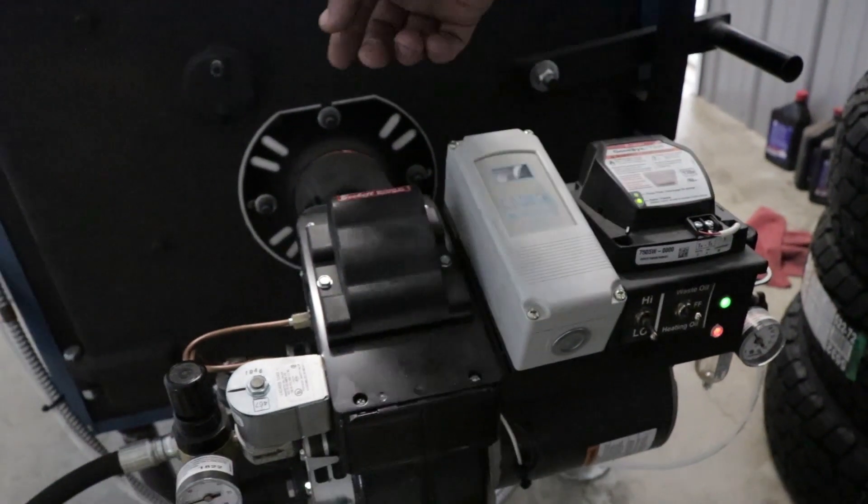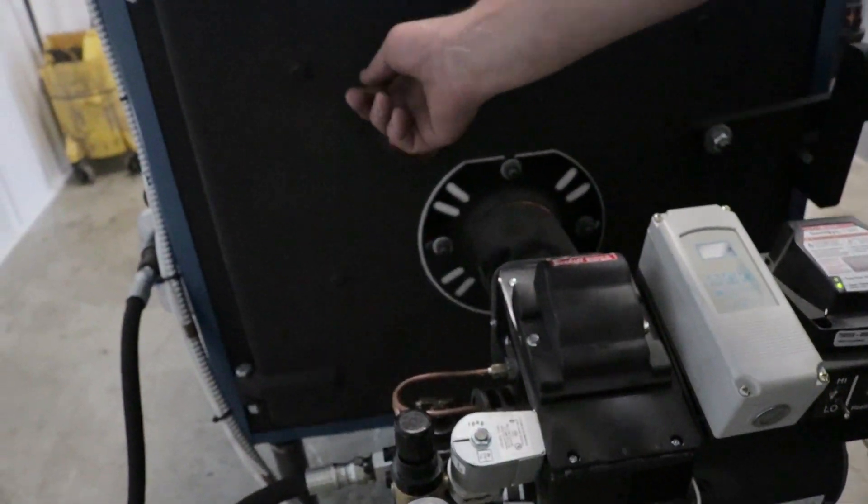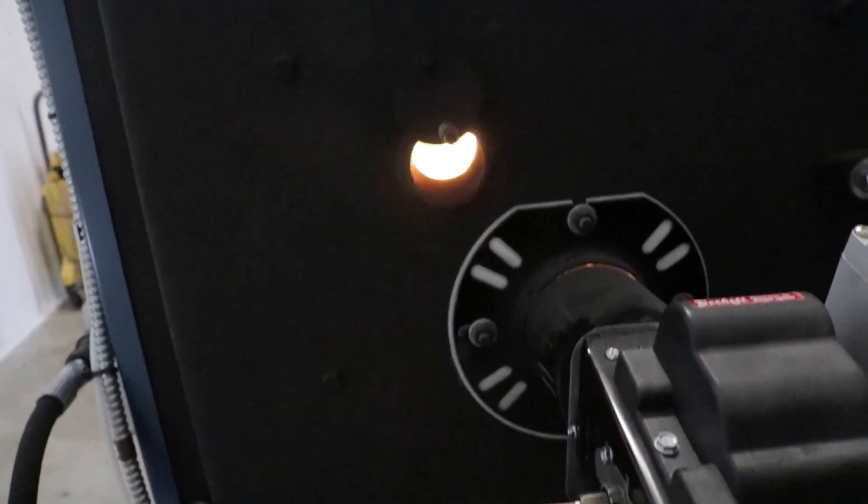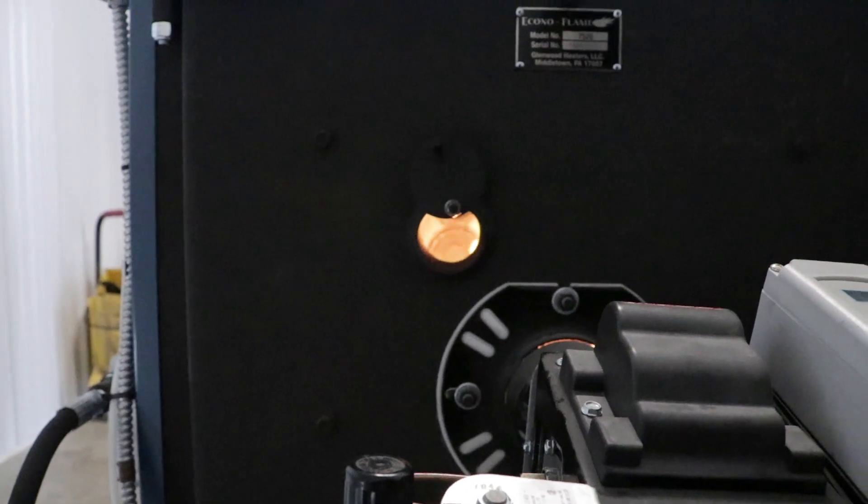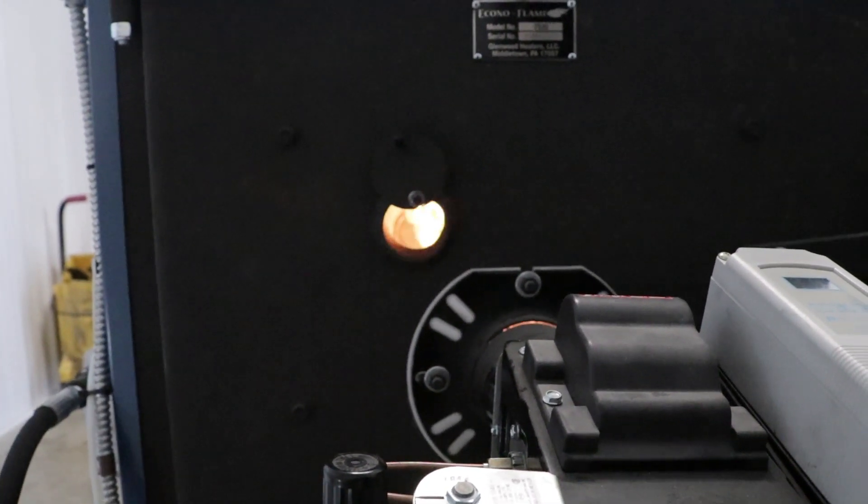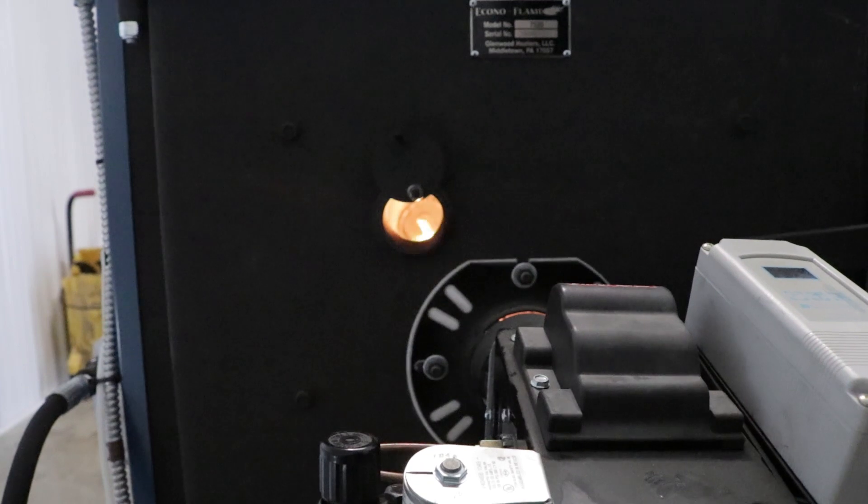This is a little access door for you to inspect the flame safely. You can see that you want a nice, puffy flame without a lot of sparks.